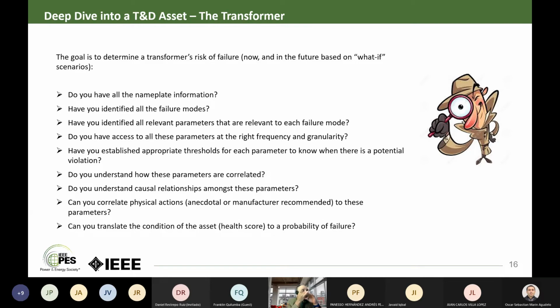Then the other thing we need to understand is, for each of these failures, what are the parameters that can define and describe these failures? For example, if I'm talking about the failure of an accessory like the fan in a transformer, the parameter I will look at is how many times the fan came on and off in a day. That's the parameter I will monitor.